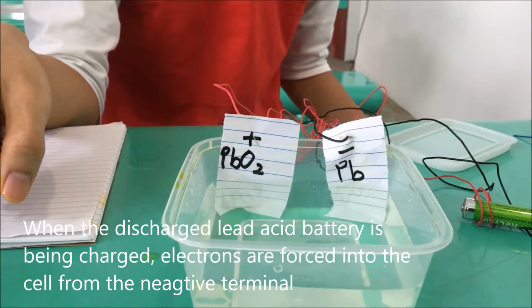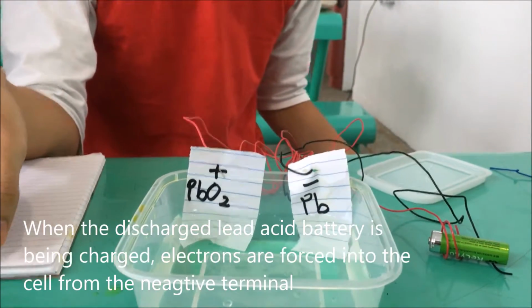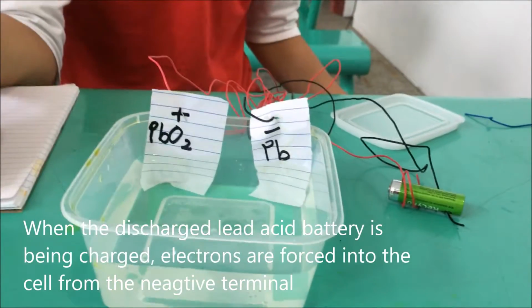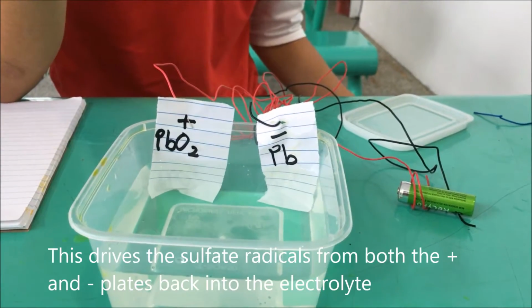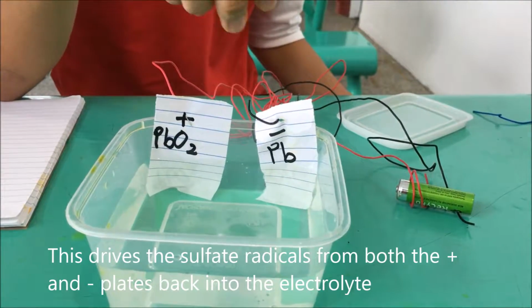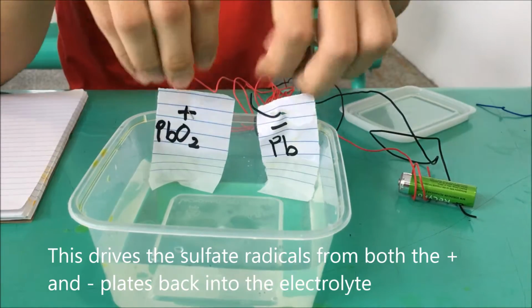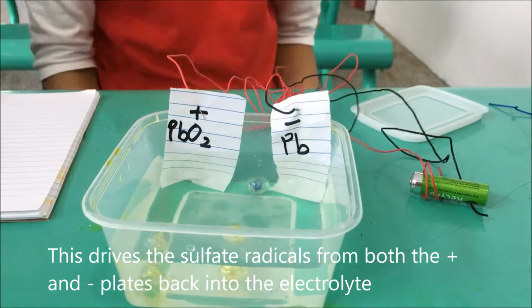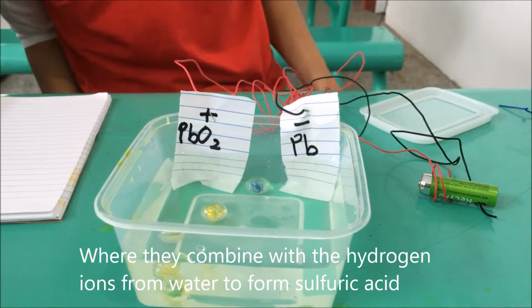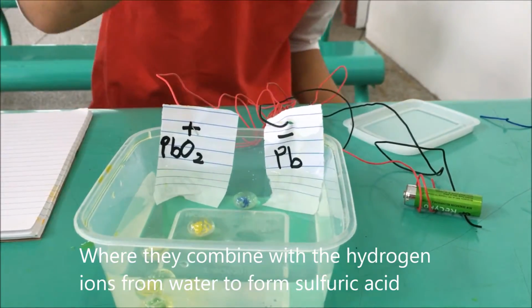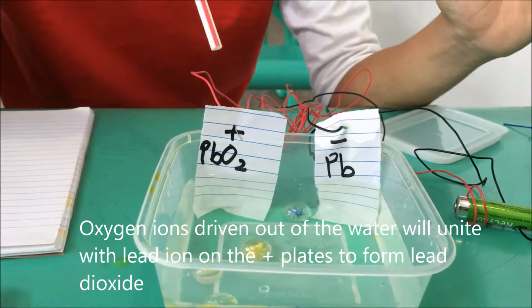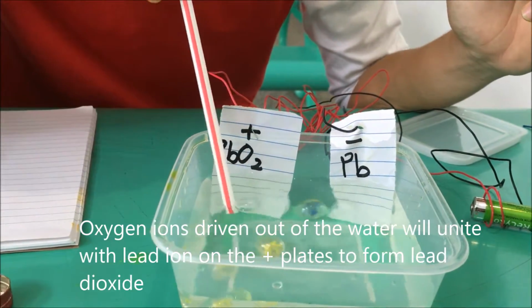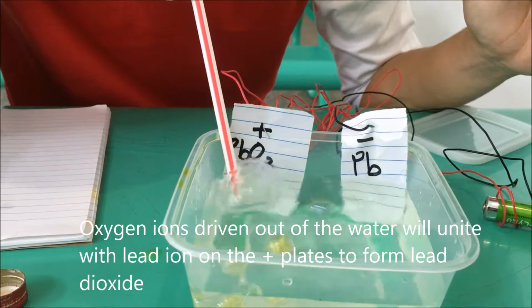When a discharged lead-acid battery is being charged, electrons are forced into the cell at the negative terminal. This drives the sulfate radicals from both the positive and negative plates back into the electrolyte, where they combine with the hydrogen ions from water to form sulfuric acid. Oxygen ions driven out of the water will unite with lead ions on the positive plate to form lead dioxide.